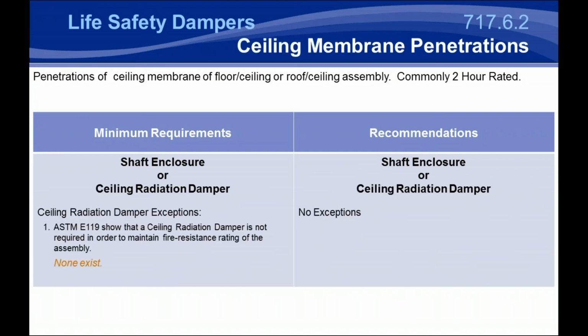And then we get into ceiling membrane penetrations. I talked a little bit about this in corridors. As a damper manufacturer, there are 3 basic types of ceiling assemblies that we deal with. Of course, there are hundreds of types of floor ceiling assemblies and roof ceiling assemblies in the UL Fire Resistance Directory. But as a damper manufacturer, we group them into 3 categories.